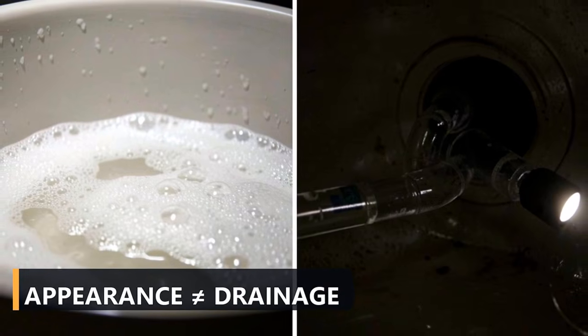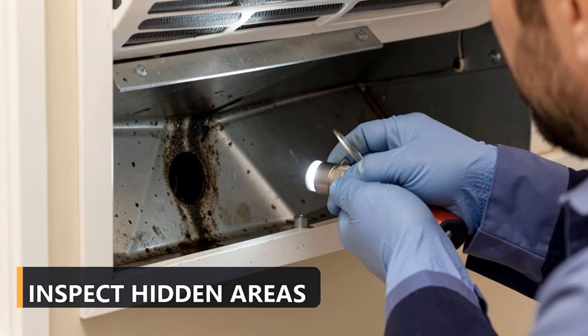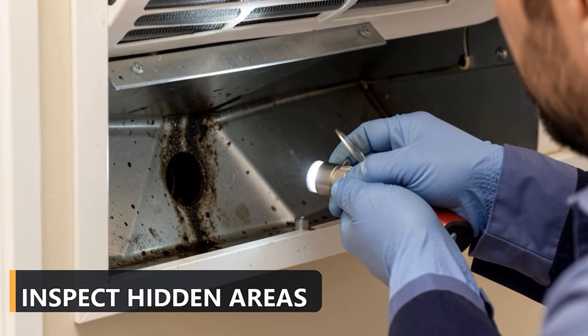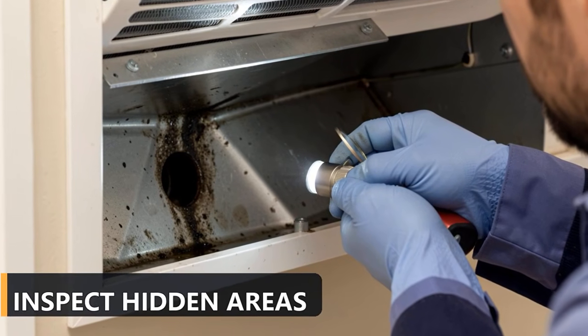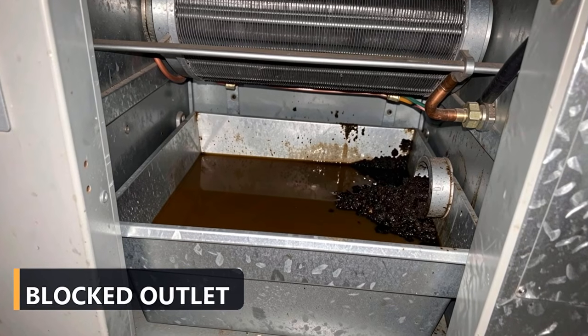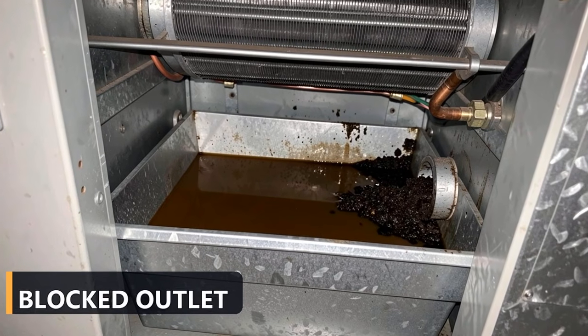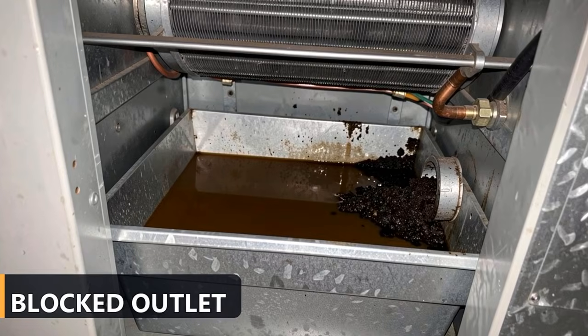But now examine the corners, the outlet opening, and the underside of the coil. Thick debris remains where the liquid never reached. More importantly, the pan may be cracked, rusted, poorly sloped, or overflowing because the outlet is blocked. No chemical can repair a damaged pan or correct its pitch. The real test is drainage.